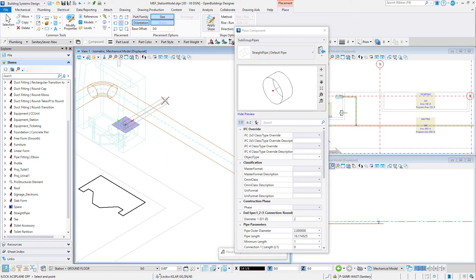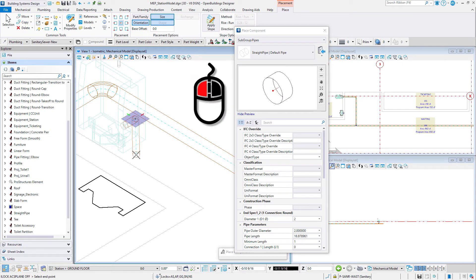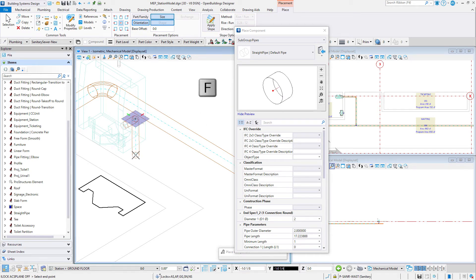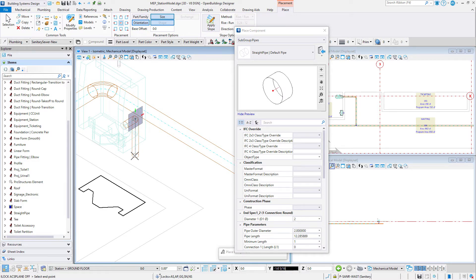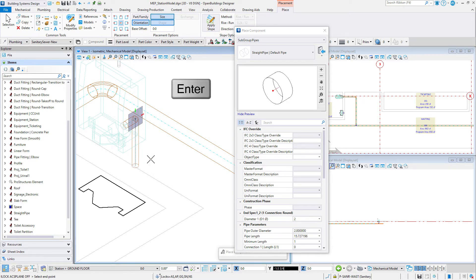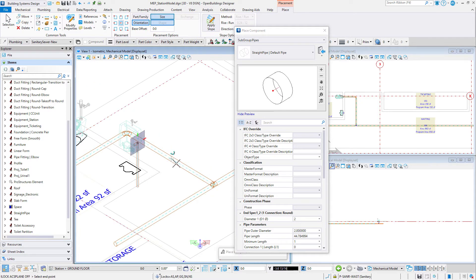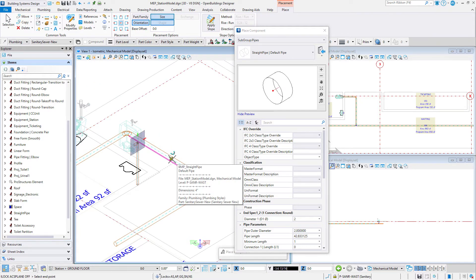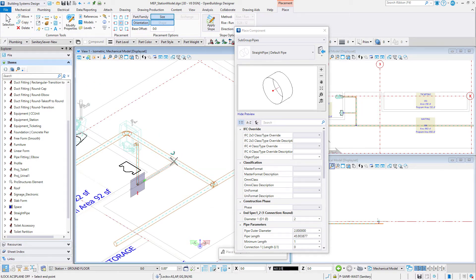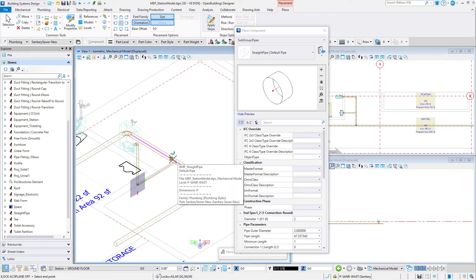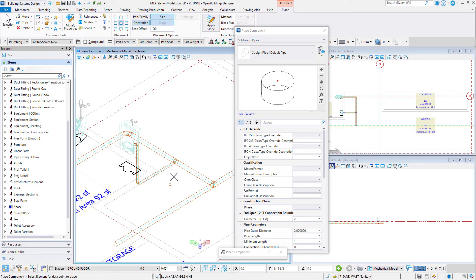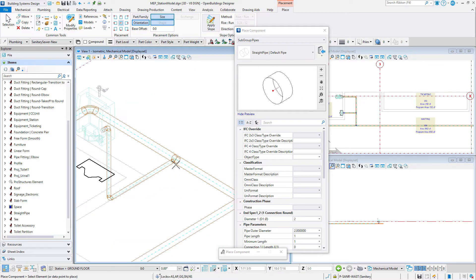Using AccuDraw, place the pipe horizontally 4 inches, and then data point to accept. Type F to rotate the AccuDraw compass to a front orientation. Move the cursor down and type enter to lock the AccuDraw axis in the vertical direction. Snap to the branch pipe from the toilet to align the new pipe and data point to accept. Finally, place the pipe horizontally connecting it to the branch pipe from the toilet.